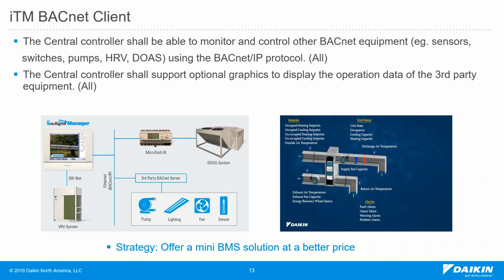When you use that function, most of the time the owner requests how to display that equipment in a graphic display. We developed GBEC files that can be used as a graphic display, and after that we can drag and drop all the data points inside that graphic display, similar to the picture shown here. So you can display all the set points, unit status, and all the alarms on the graphic. And if we don't have a graphic for specific equipment, you can create an image and put the graphics on it. You can create your own graphics and customize them as you want, and put the data points on top. That's how we use our BACnet client as a mini BMS system.